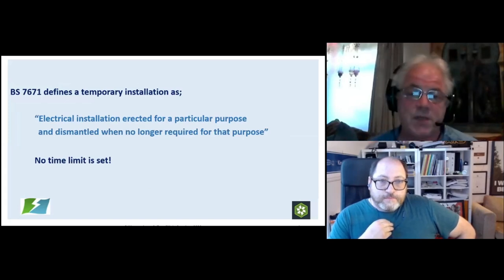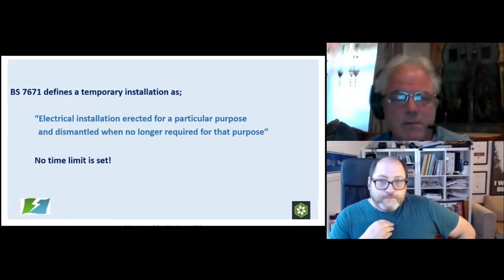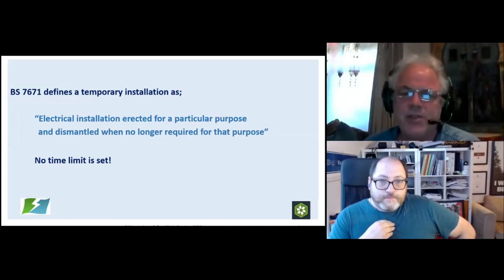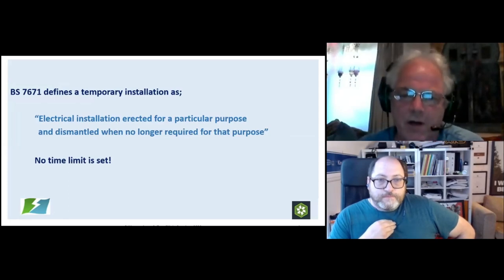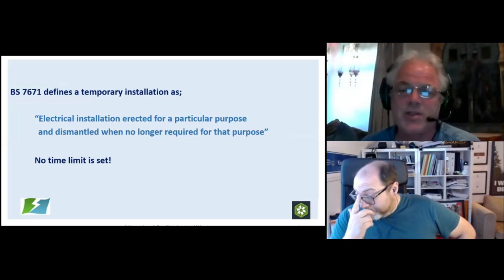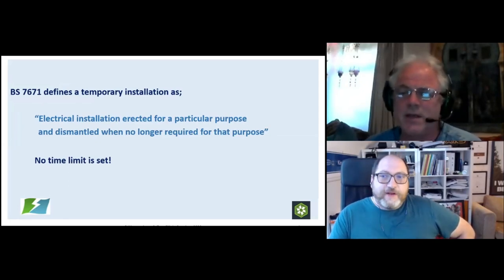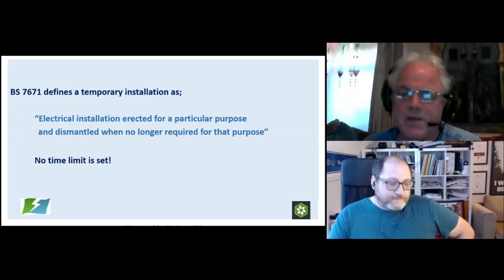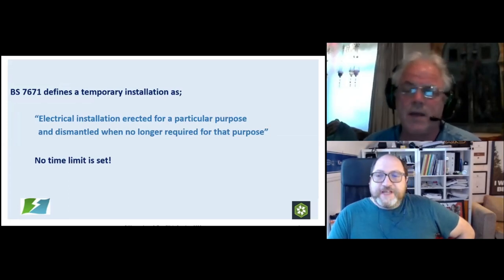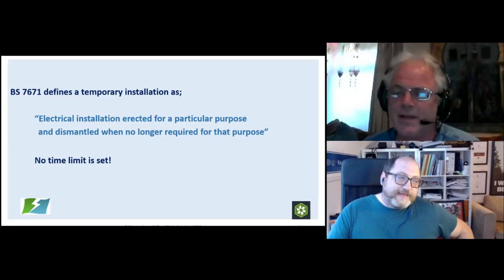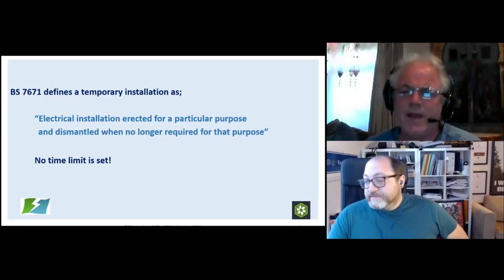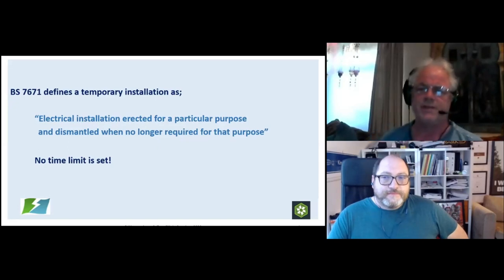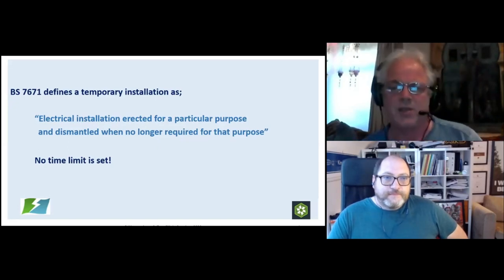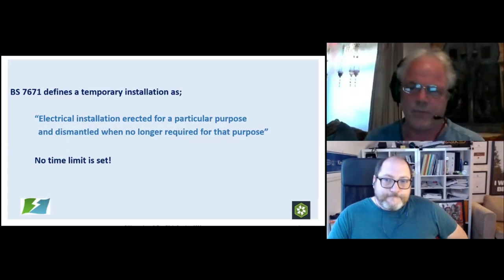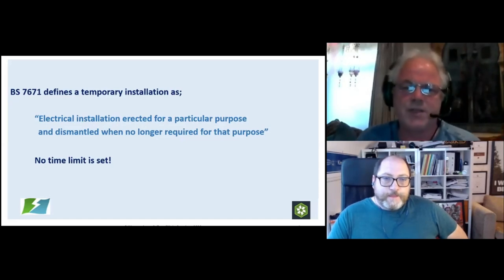BS7671 defines a temporary installation as an electrical installation erected for a particular purpose and dismantled when no longer required for that purpose. There is no time limit set. And this is one of the common questions I get asked: how long is temporary? Well, we've known temporary electrical systems that have been in for a number of years, or intended temporaries that just got neglected and forgotten. Well, we might need that again, or we'll leave that in. And it comes to a point where you have to take a common sense approach. If you want this as a permanent thing, it needs to be done properly. But effectively, a temporary system is one that is pulled out when it is no longer required for that purpose.